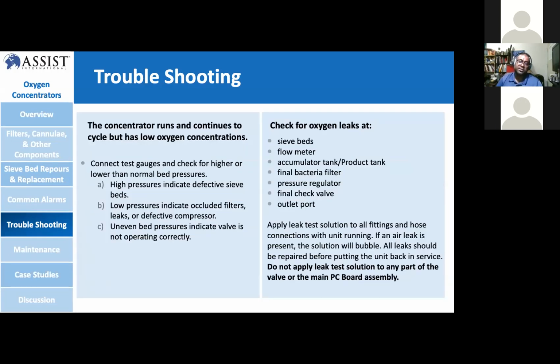So if the oxygen concentrator runs on a continuous cycle but has low oxygen concentration, high pressure can indicate a defective sieve bed, low pressure can indicate an occluded filter, leak, or defective compressor, and uneven bed pressure indicates a valve not operating. Sometimes, due to humidity, the sieve bed becomes harder, so you get uneven readings as well. So check for oxygen leaks at the sieve bed, flow meter, then product tank, and check the bacteria filter. Is there any blockage, or is it broken? And check the valve and outlet port, all that.